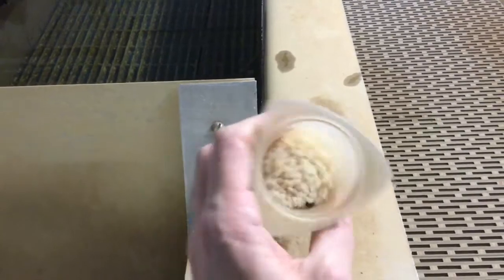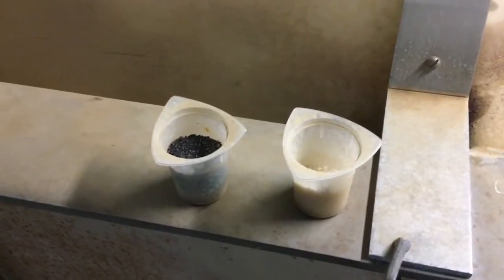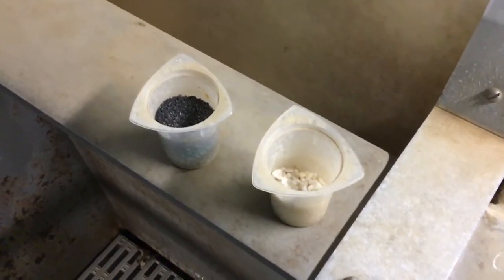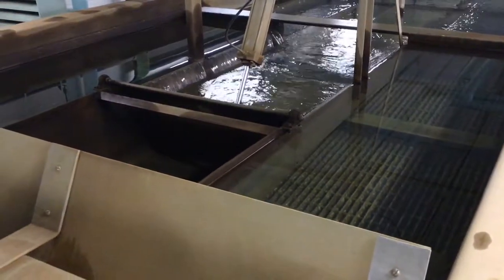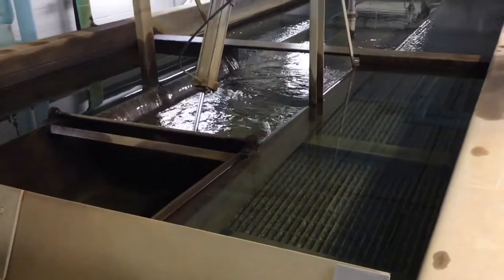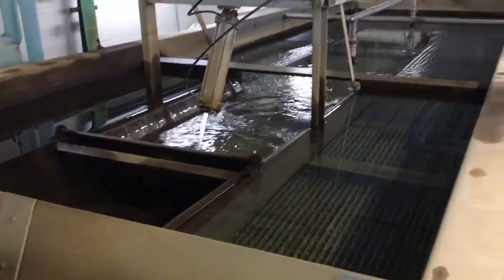In the clarifier stage, I can actually show you what's in there: millions of these little plastic BBs. Basically from the level of my feet all the way down to the floor, they're filled with millions of those. And those are coated in a compound called aluminum sulfate, and also an anionic polymer, which is just a negatively charged polymer. What that will help do is help any fine or particulate particles floating around in the raw water, so any dirt or small microbes, coalesce or clump together and form bigger chunks, because the bigger a chunk of something is, the easier it is to then filter it, right? That makes a lot of sense.